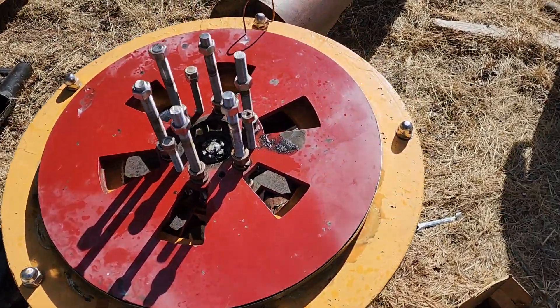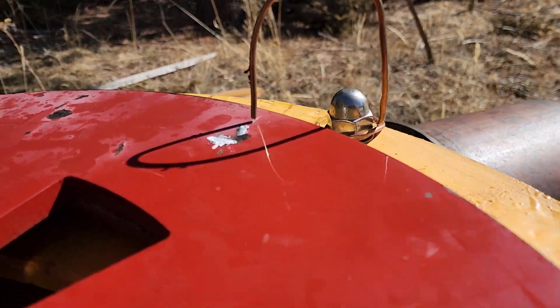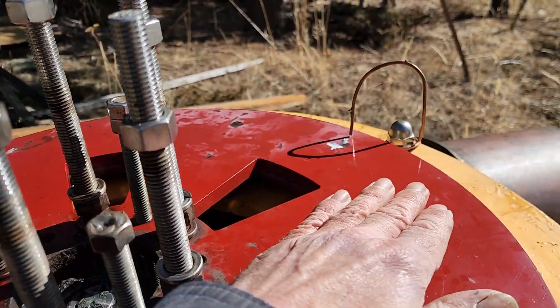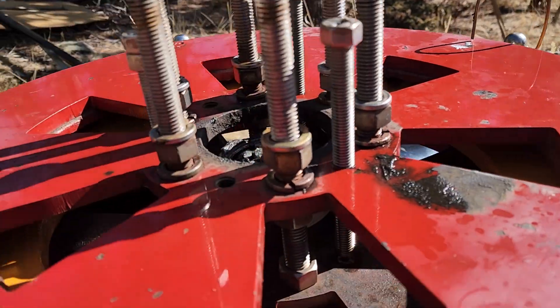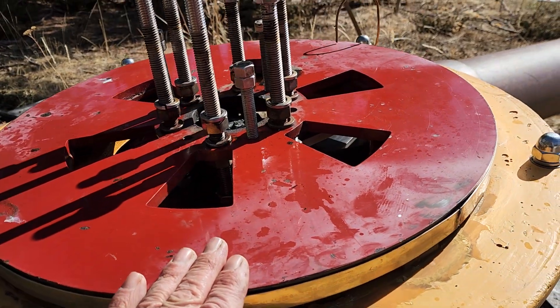We've tightened the bearing. We used this gauge — a bent piece of copper wire — visualizing the gap, and jacking screws to get the rotor running true. And once we got it true, we raised these nuts underneath, all around, to hold the front magnet rotor where it is.